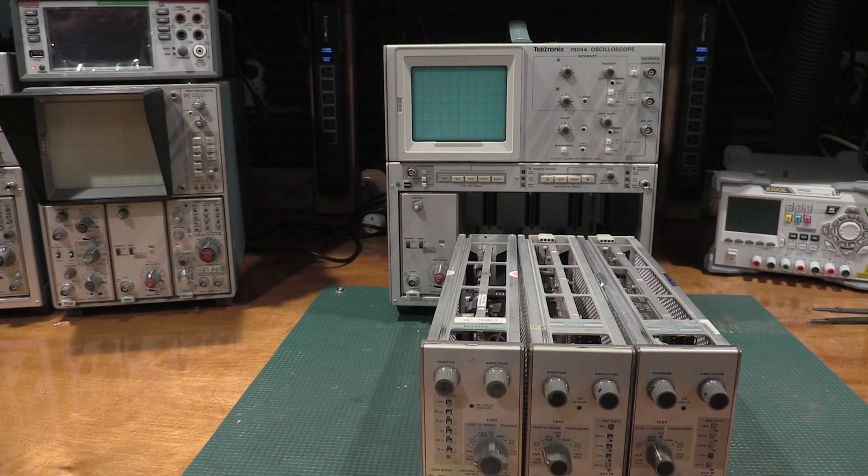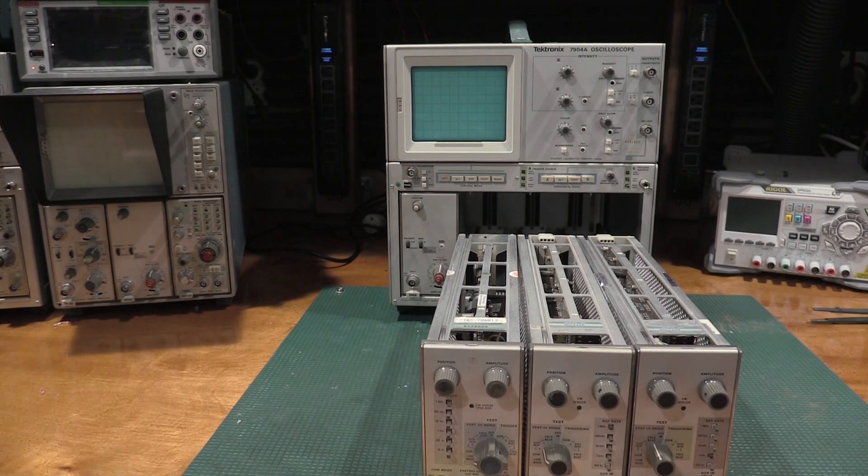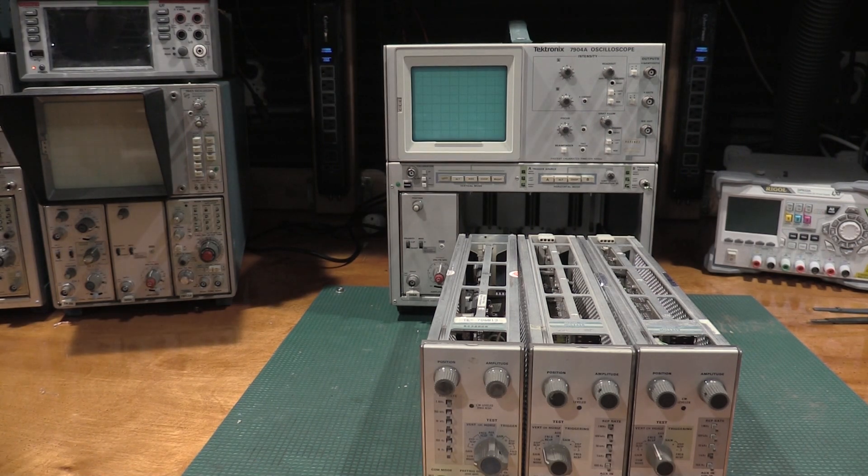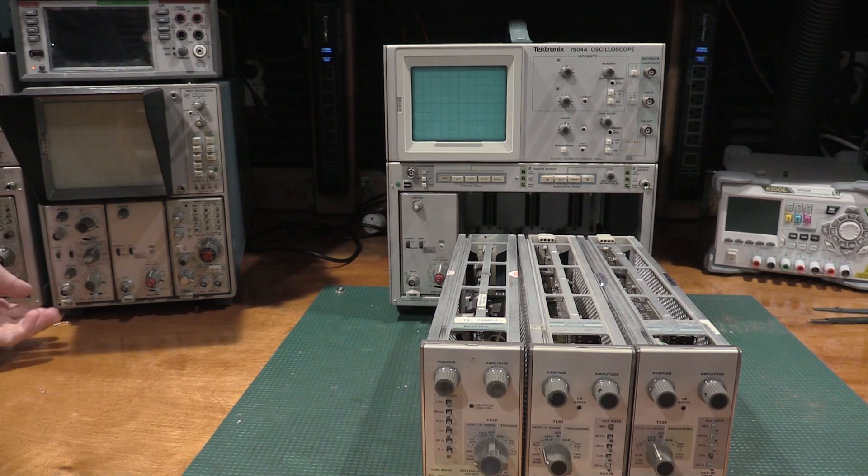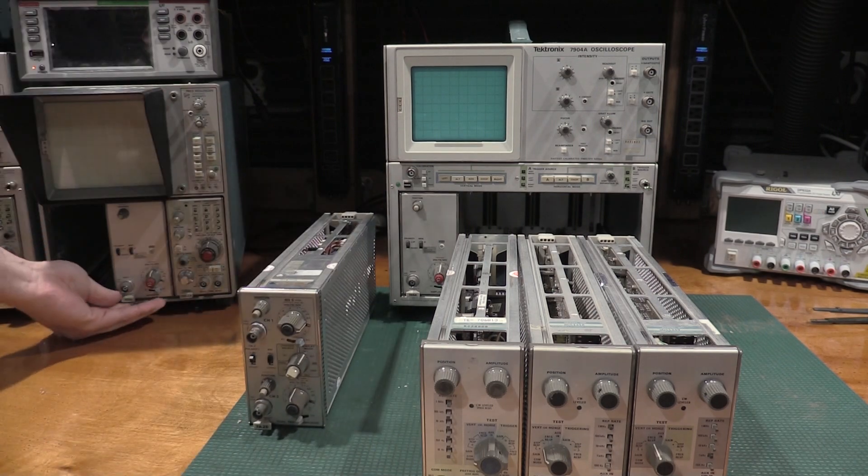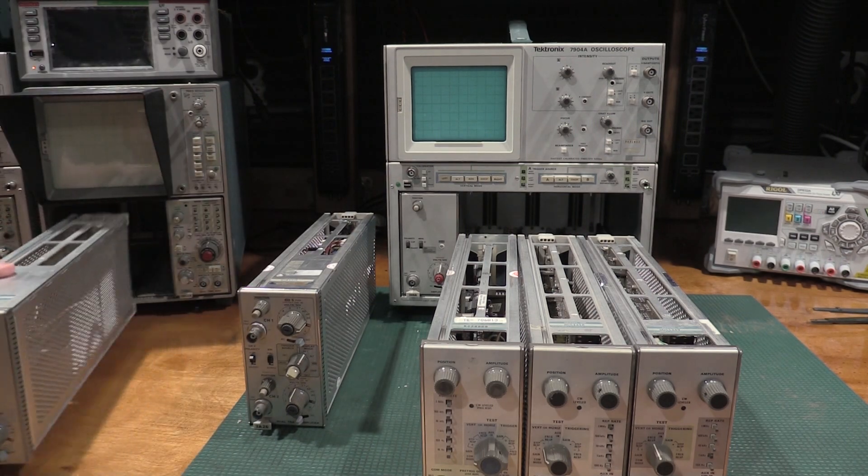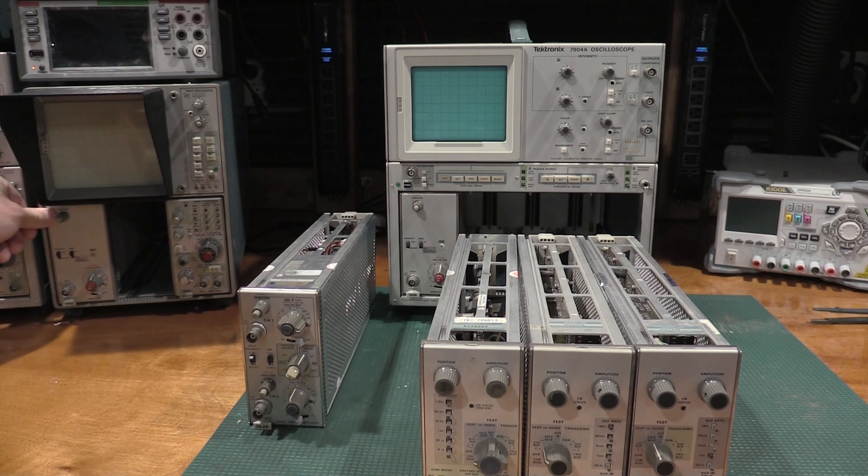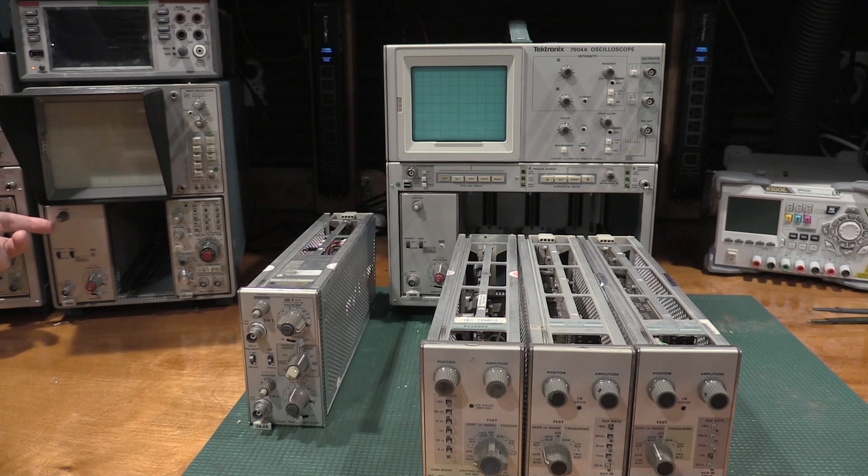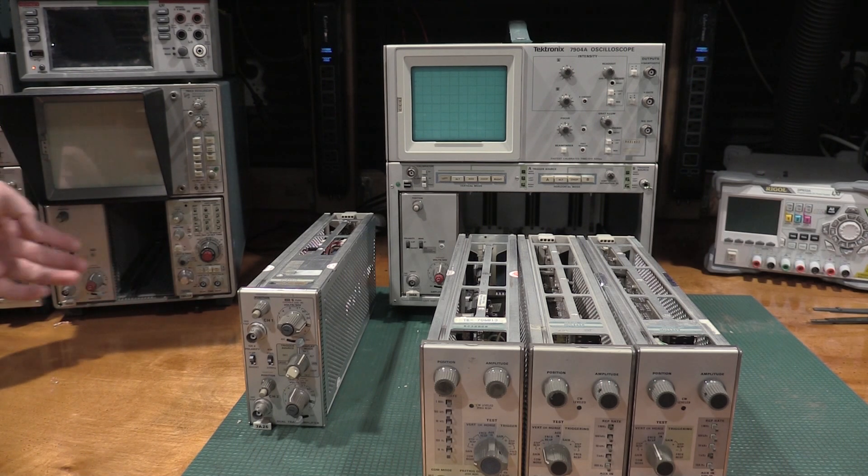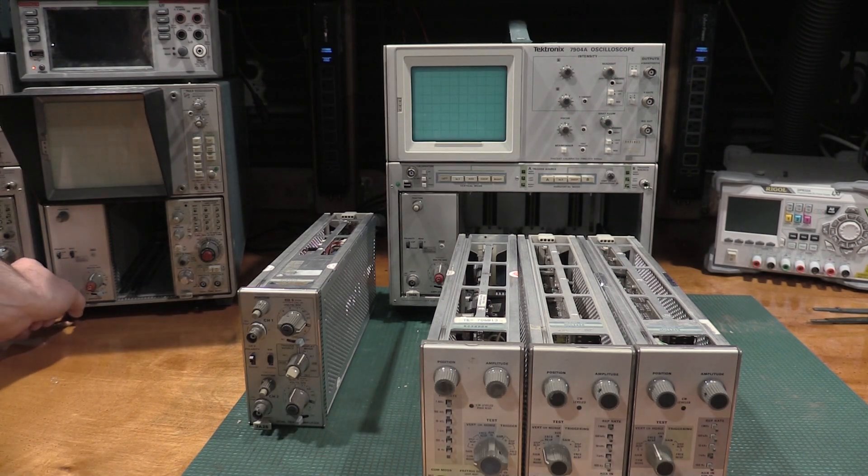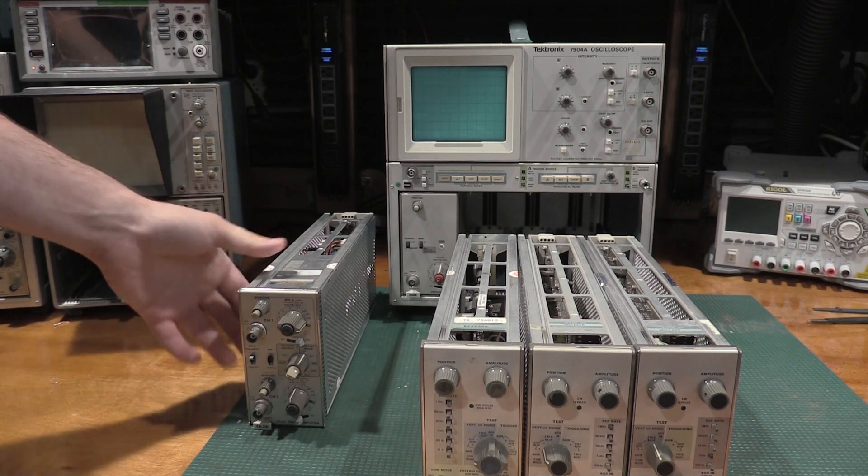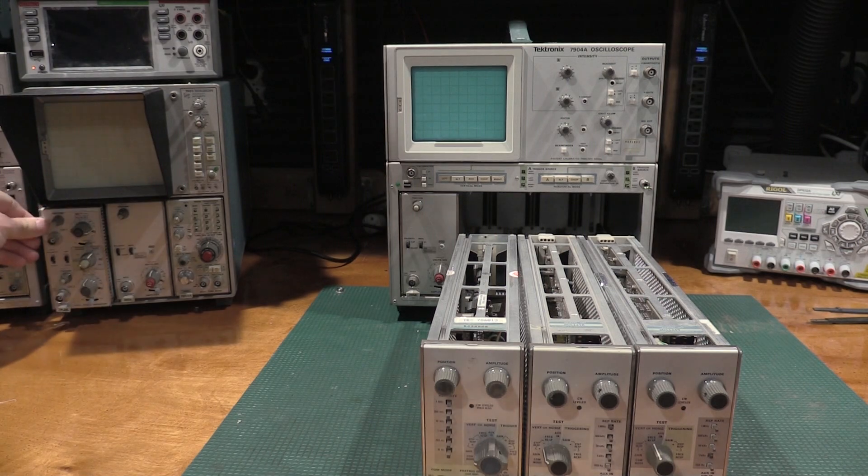The other thing, so what the signal standardizers and plug-ins are actually doing is standardizing the response of the individual bays. So if I pull this out and move this over, the bays are within a tolerance where this is still giving me valid measurements because the response between the two ports is standardized and roughly the same because they were aligned with the same signal. Obviously this is off, so I can move these around all day.